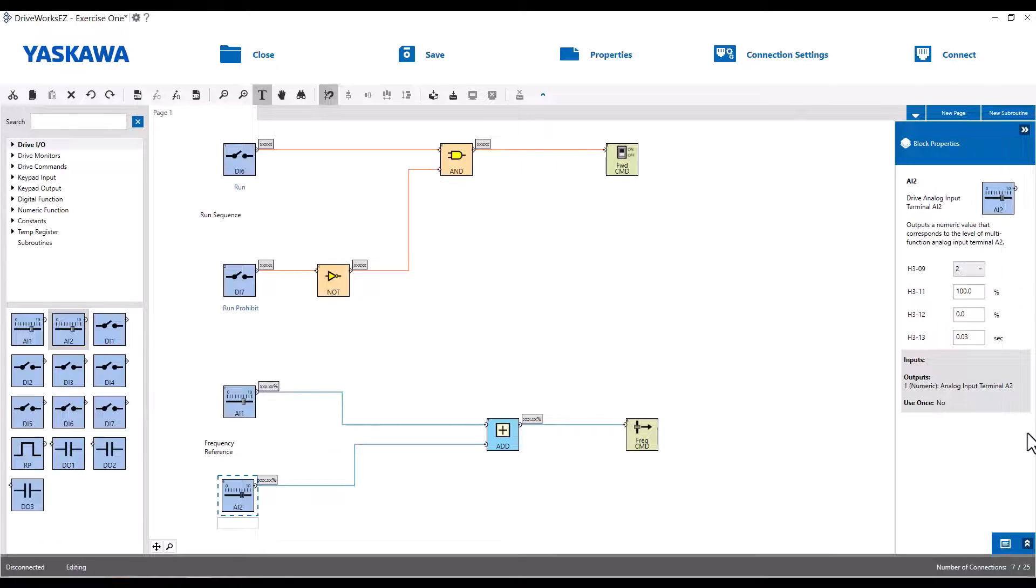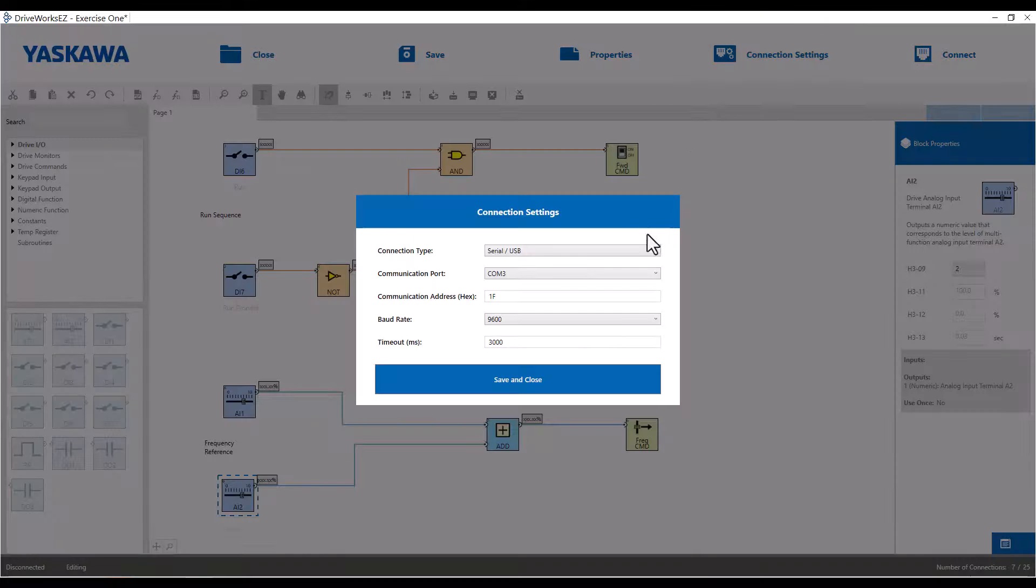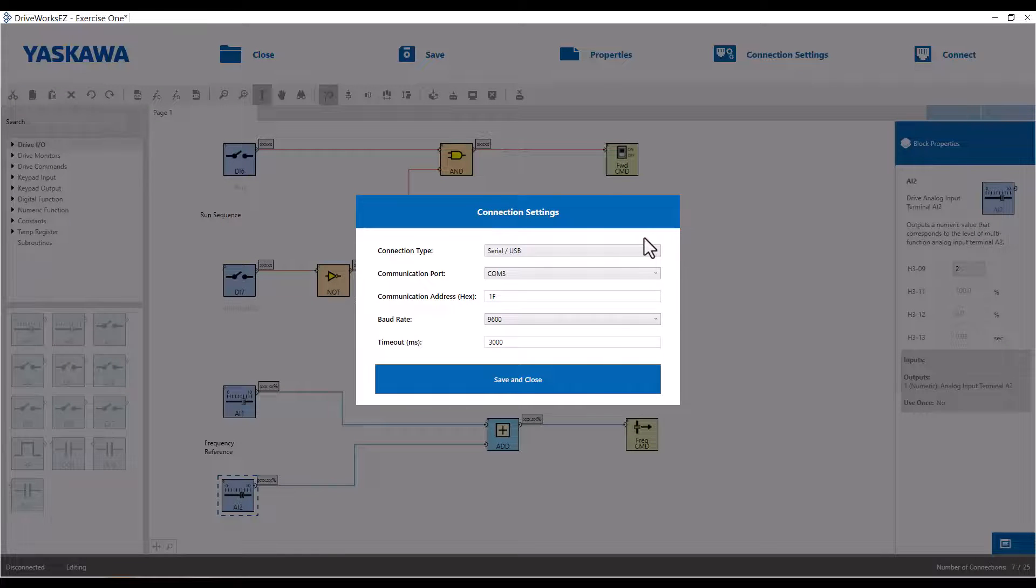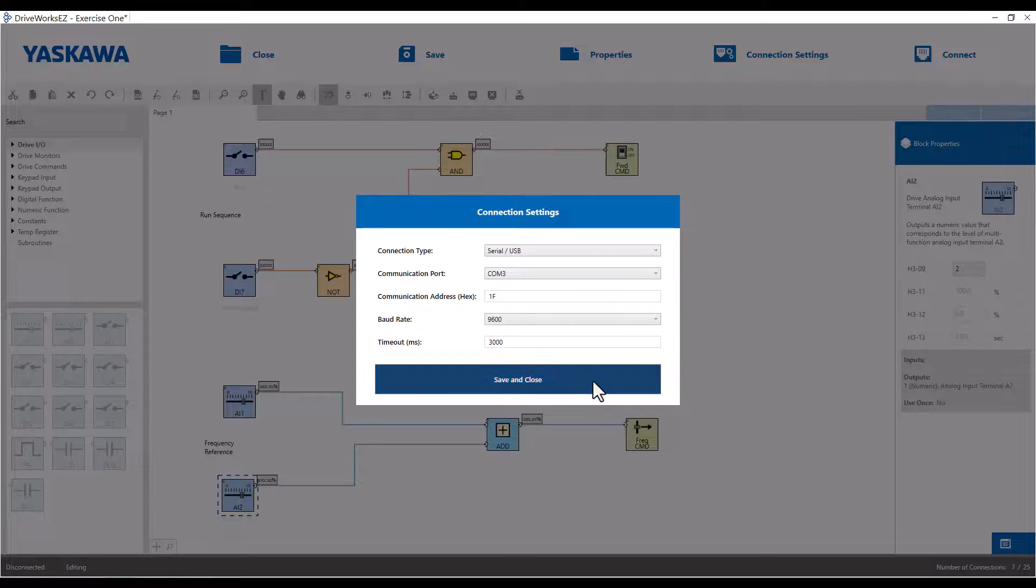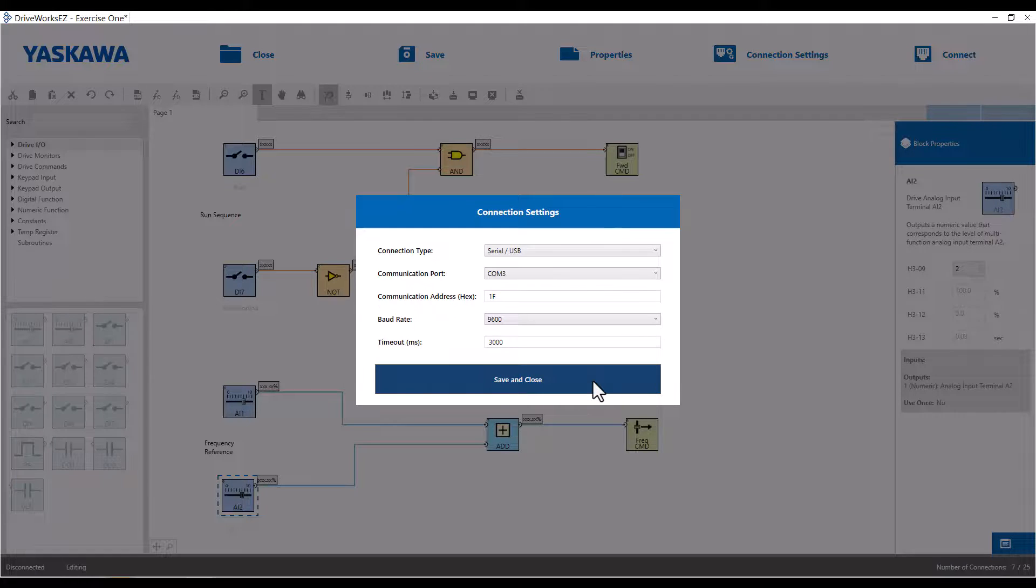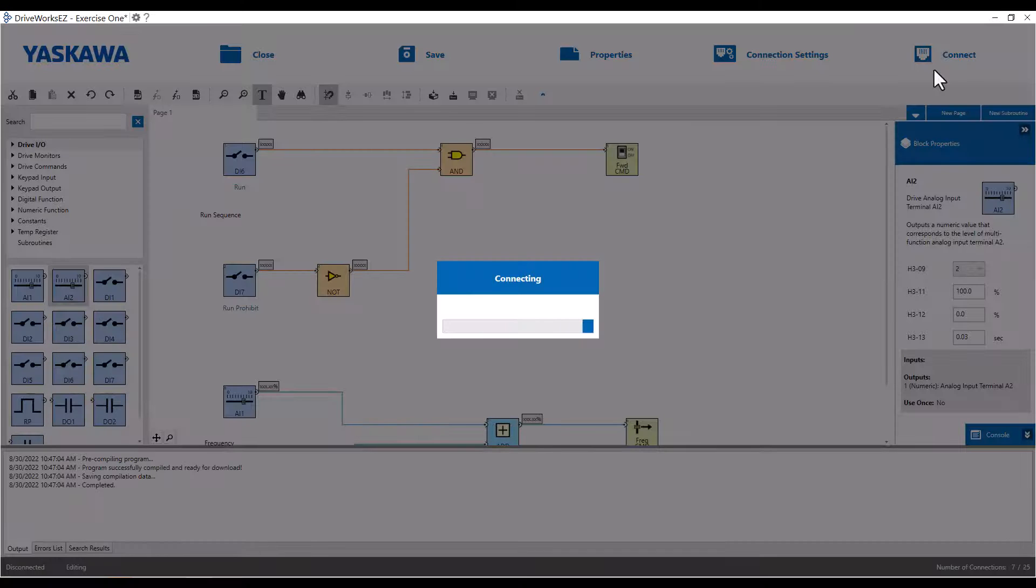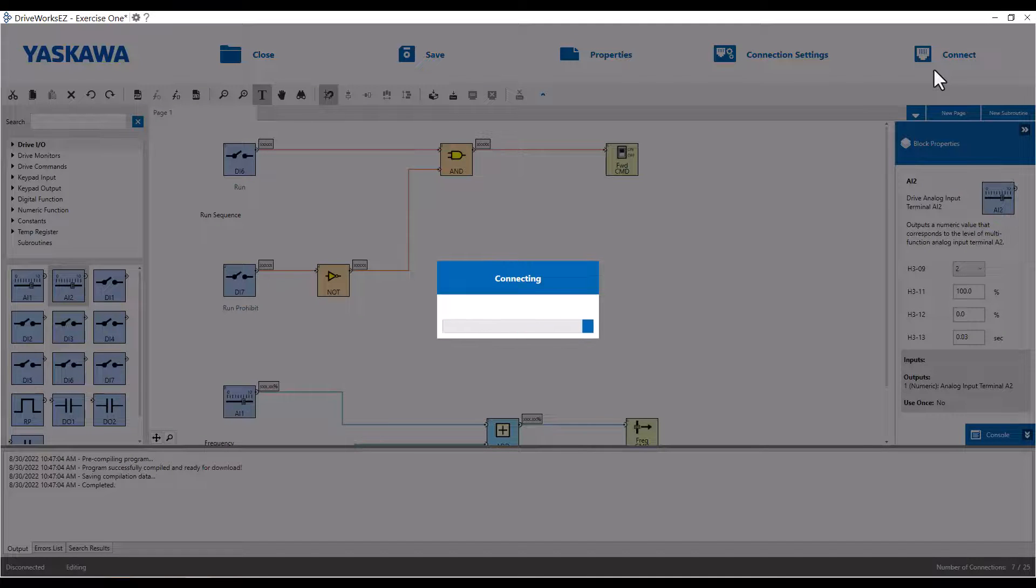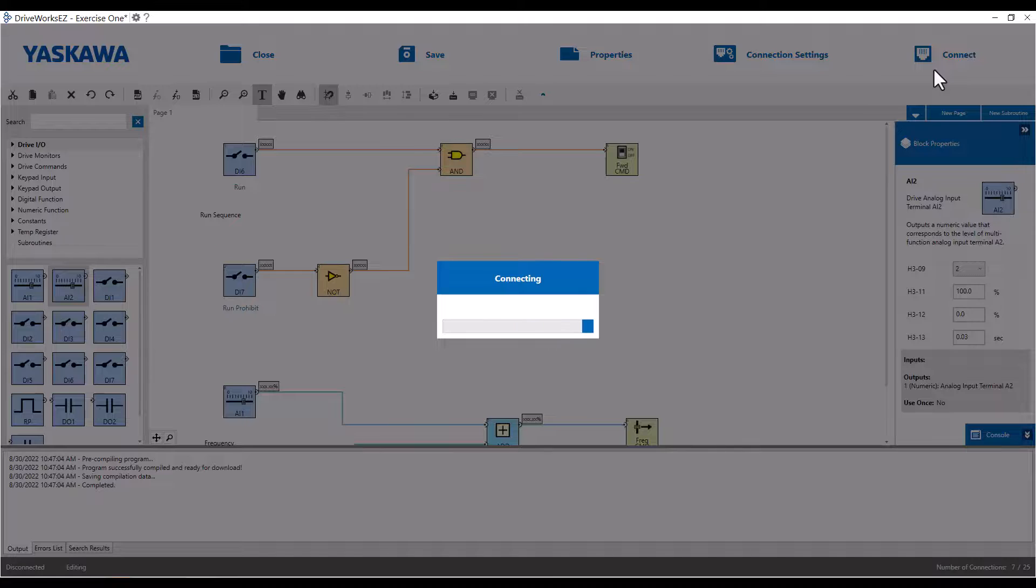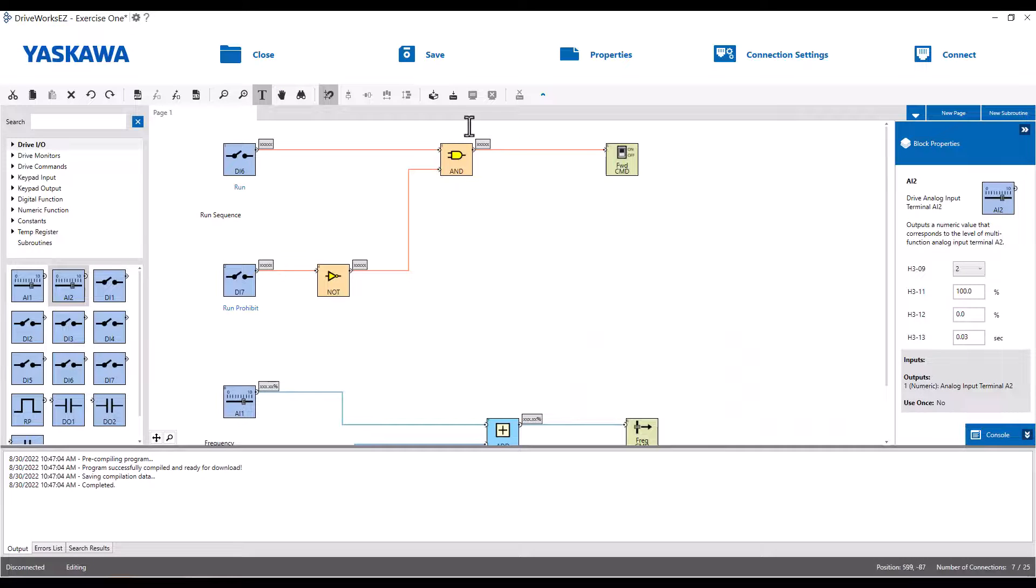To double check your connection settings, just select the Connection Setting button. I'm actually going to set it to Serial USB because I'm physically connected via USB to the drive. Click Save and Close. Before we can download, we need to connect to the drive using the top Connect button. Then we can select the Download button on the lower toolbar.